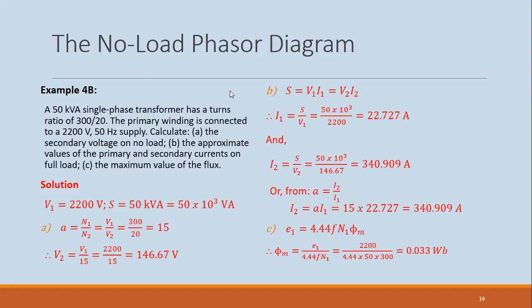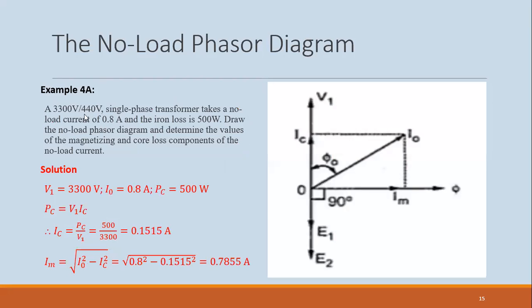But for now, just take it that the secondary voltage is what we'll be using to determine the apparent power rating on the secondary side. So V2 times I2 gives you this, and this is rated at — this is what you should be getting out of the transformer on load. So when the transformer is loaded, this is what you should be getting out, all right?